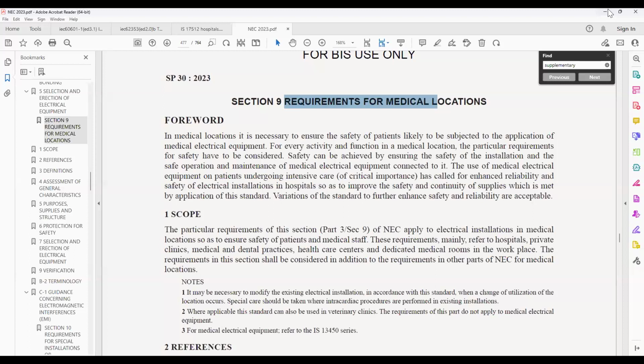Accordingly, medical equipment is classified into class 1 medical equipment and class 2 medical equipment, sometimes with a metal body and sometimes without. These equipments have applied parts. Applied part means the part of the biomedical equipment which is either touching the body of the patient or bypassing the skin and going even up to the heart. So these applied parts are classified. The dangerous part is, in case of any excess energy through the applied part, the patient may be electrocuted. We will end up with a very critical situation. So after every repair, you have to test and calibrate the equipment and ensure that the energy going into the patient is within the limit. Otherwise, it can create a hazard.